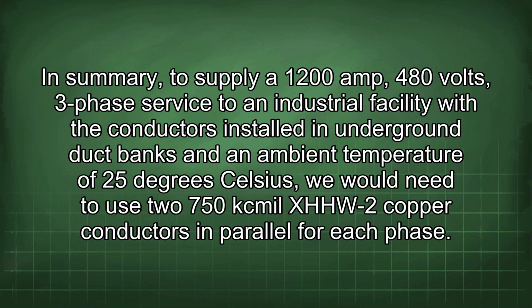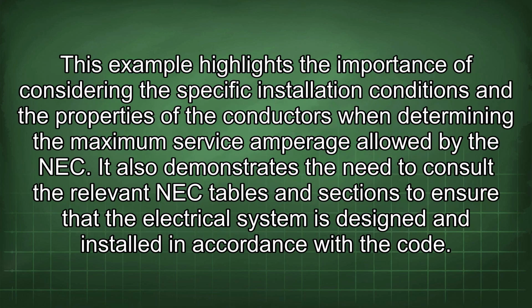In summary, to supply a 1200 amp, 480 volt, three-phase service to an industrial facility with the conductors installed in underground duct banks and an ambient temperature of 25 degrees Celsius, we would need to use two 750 kcmil XHHW-2 copper conductors in parallel for each phase. This example highlights the importance of considering the specific installation conditions and the properties of the conductors when determining the maximum service amperage allowed by the NEC. It also demonstrates the need to consult the relevant NEC tables and sections to ensure that the electrical system is designed and installed in accordance with the code.